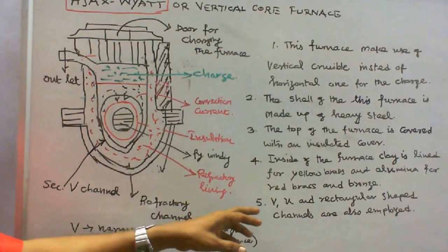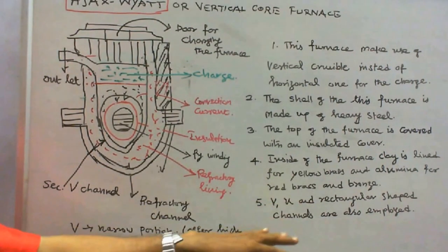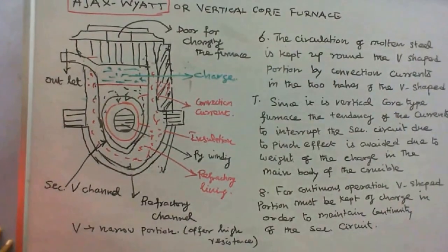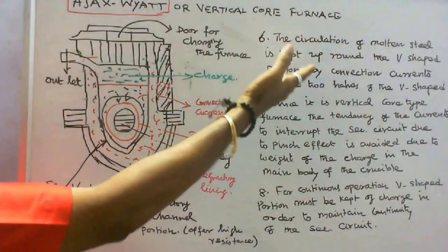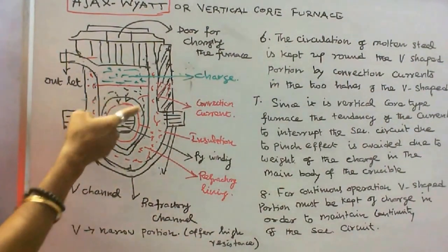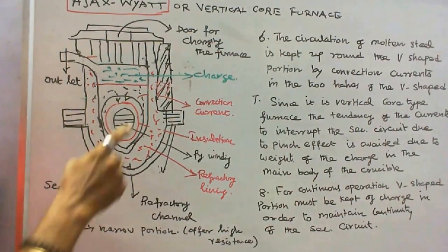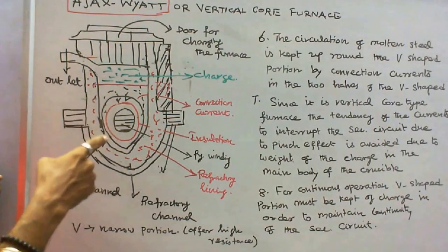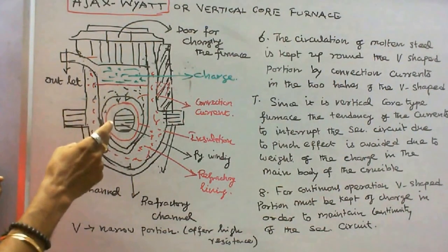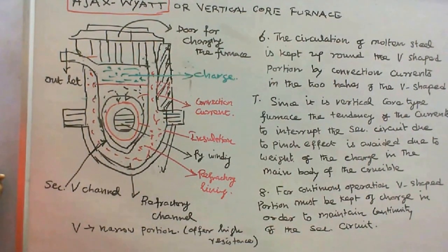Apart from V-shaped channels, U and rectangular shaped channels are also employed in this furnace. The circulation of molten metal is kept up around the V-shaped portion by convection currents. In the two halves of the V-shape, since it is a vertical core type furnace, the tendency of the current to interrupt the secondary circuit due to the pinch effect is avoided due to the weight of the charge in the main body of the crucible.